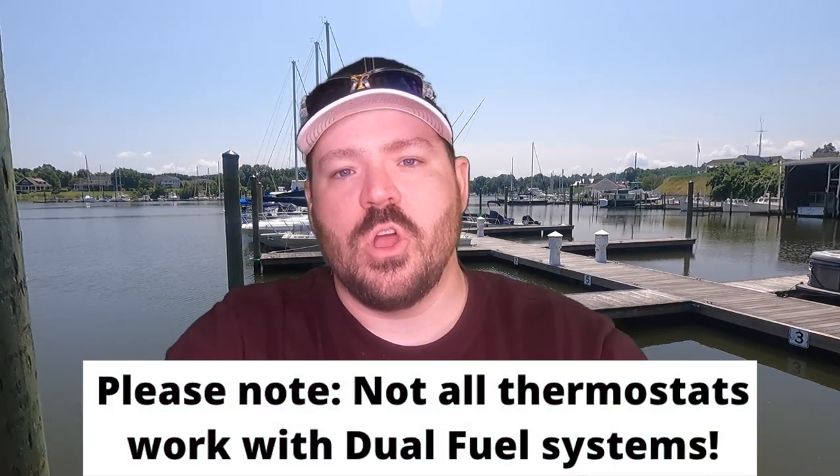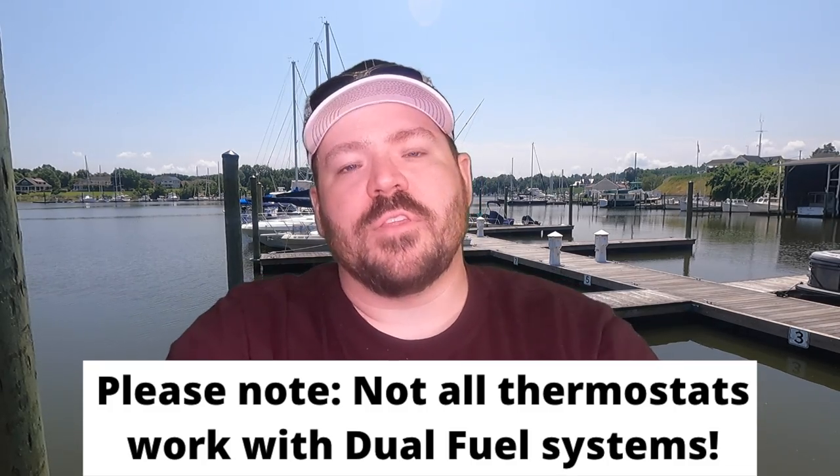Now, why does any of that matter? I would say in most cases, most of our customers, if they have natural gas, they have a less expensive utility bill and they're not usually as open to spending the money to get a dual fuel system. Does a dual fuel system cost more? Yes. A heat pump typically costs more than a straight AC outdoor unit, and you have to install some sort of system that can control that unit. In the old days we had dual fuel kits that you would install on the system — these days a lot of the smart thermostats do it for you. You just have an outdoor temperature sensor, or it can do it through the internet, though I believe the sensor is more reliable. The thermostat will decide based on what you set it up for how it will operate with that dual fuel system. So if you have natural gas, a lot of our customers don't even bother with dual fuel — the extra money they would spend just doesn't make sense.